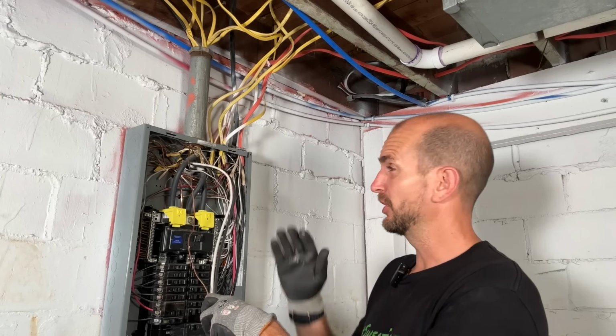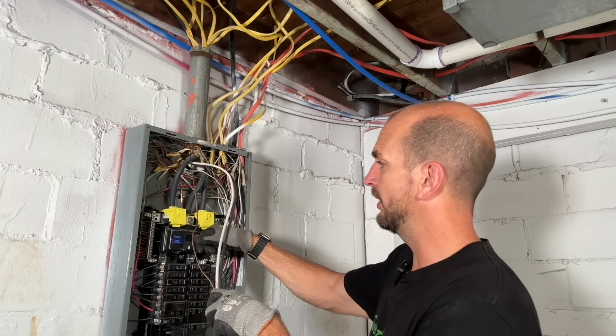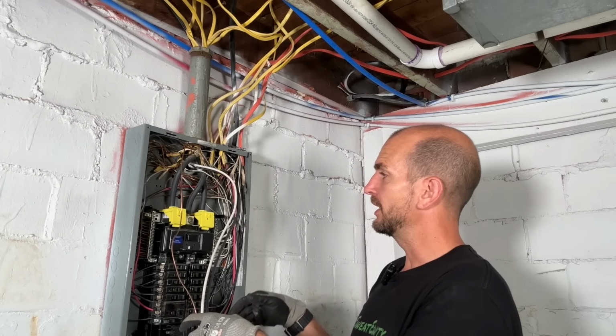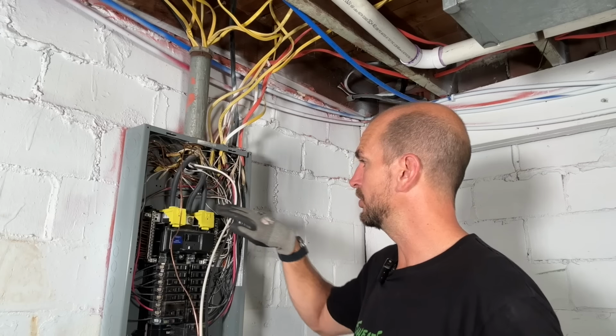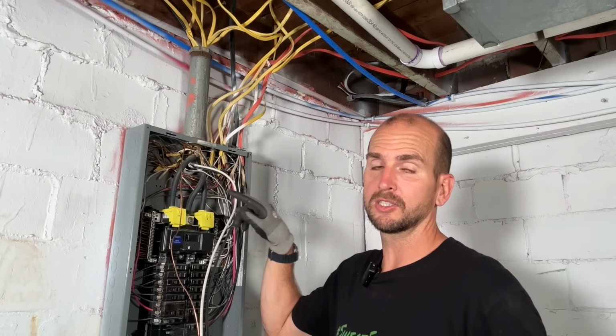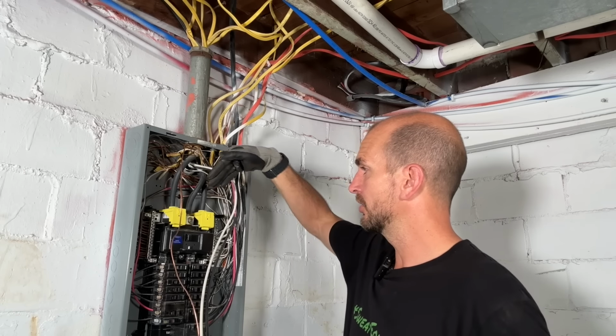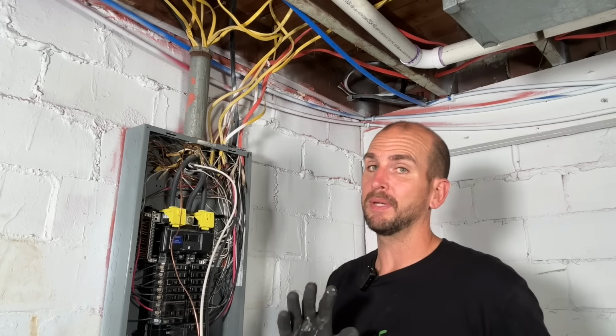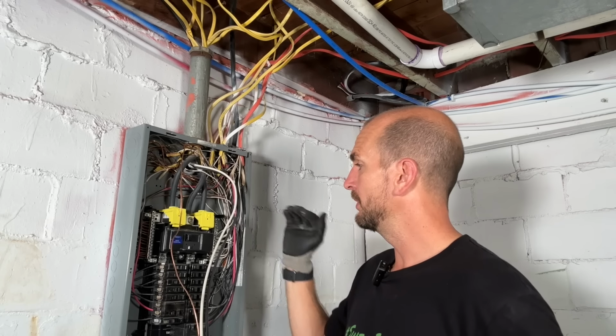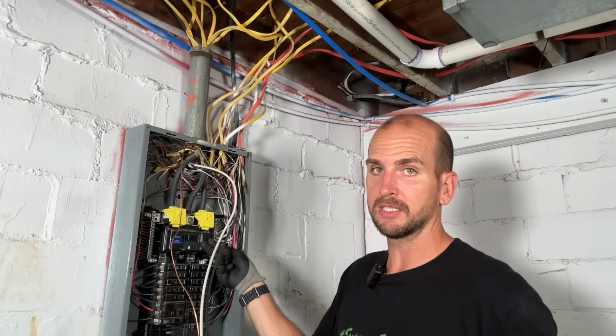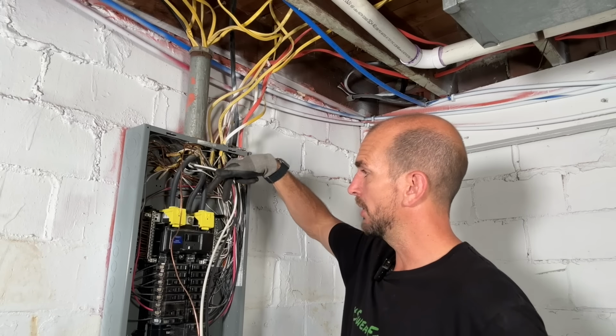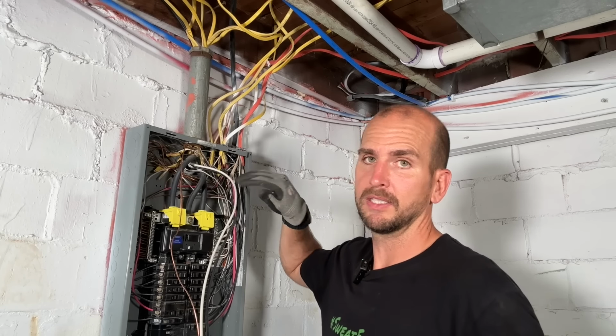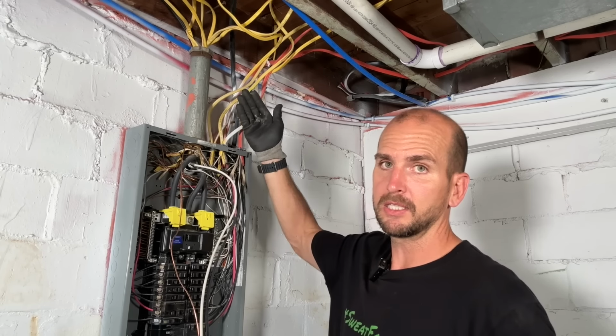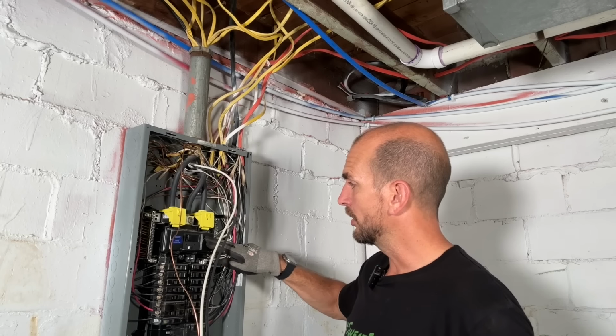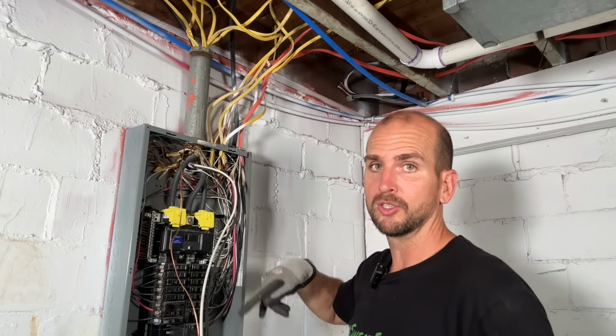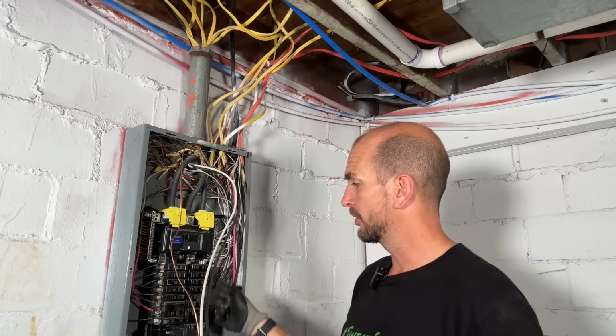As always, safety first, probably even before you get the cover off, let's go ahead and hit our main disconnect. And what I do like about the new panels is we do have covers for our main lugs off of our two different phases. So these yellow conductors will help to make it safer to work inside the panel. Because remember, even when you hit this main disconnect, the main conductors coming from your meter base, those are still live. That isn't going to neutralize those because that's coming straight from the meter base, and you are just neutralizing the two bus bars for each phase that go down through your panel.